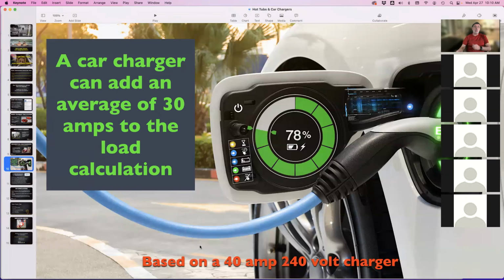Electric car chargers average about 30 amps. We're putting in a lot of them, and we're finding the demand is typically 30 to 40 amps. At 50 amps you're getting into the bigger, faster-charging car chargers, but 30 is pretty typical. Again, car chargers are taken at 100% towards the load calculation.